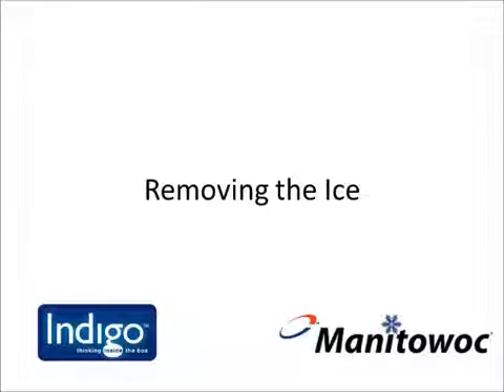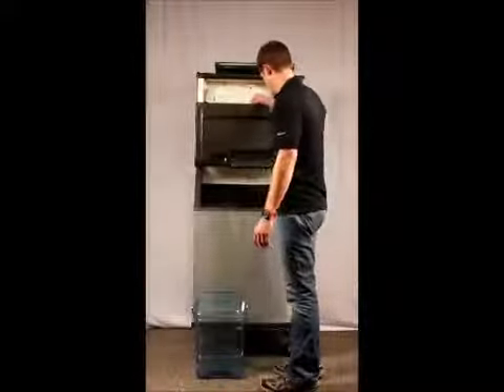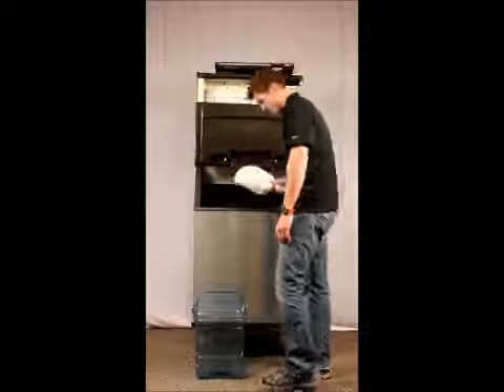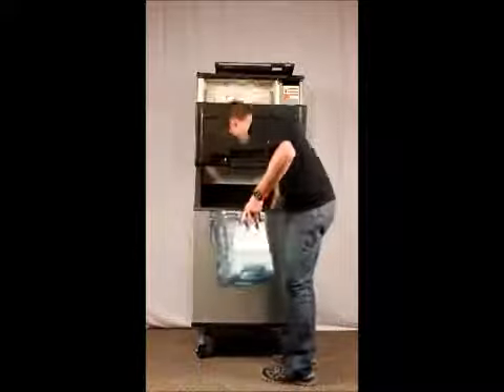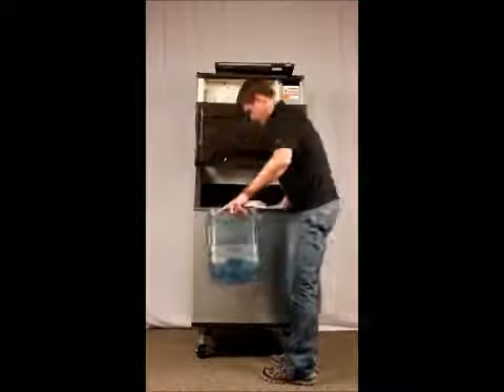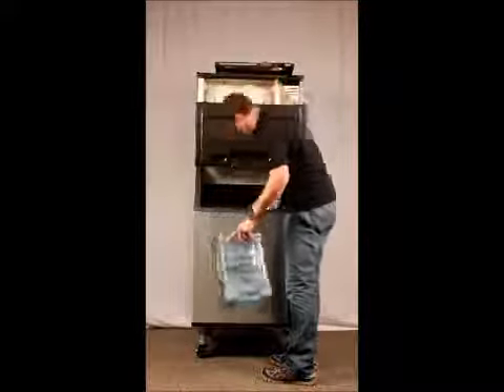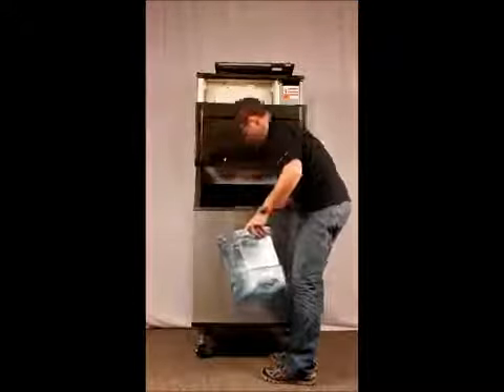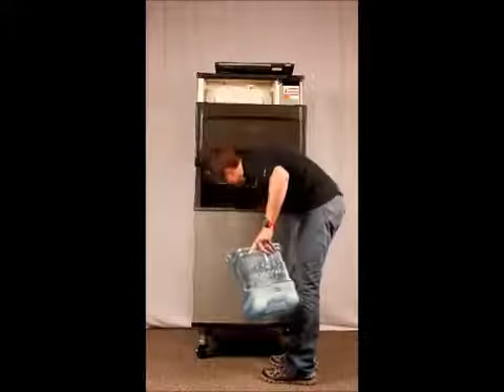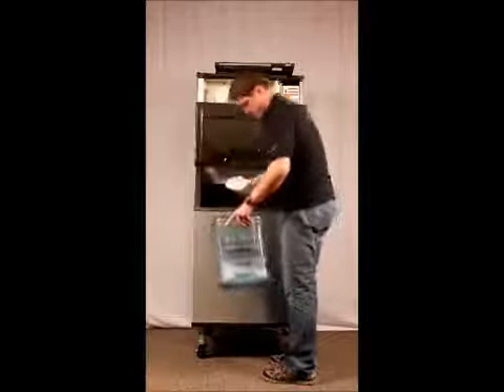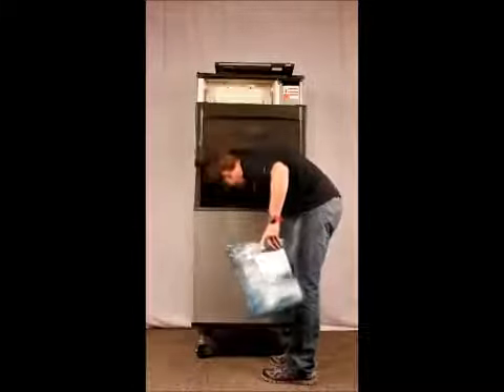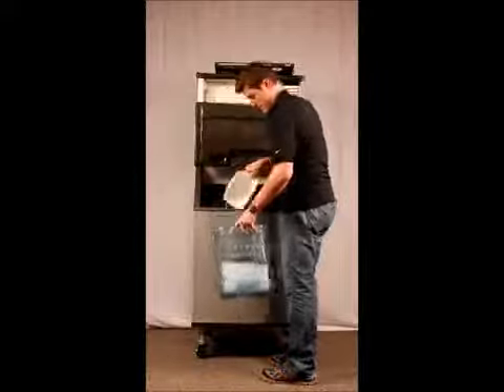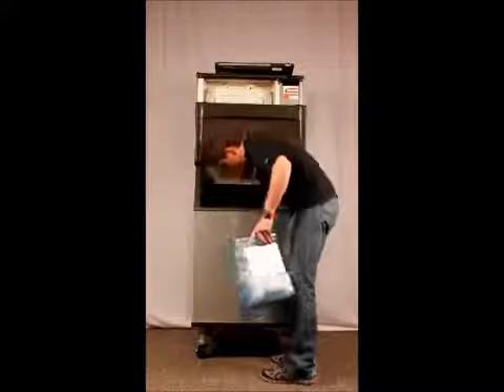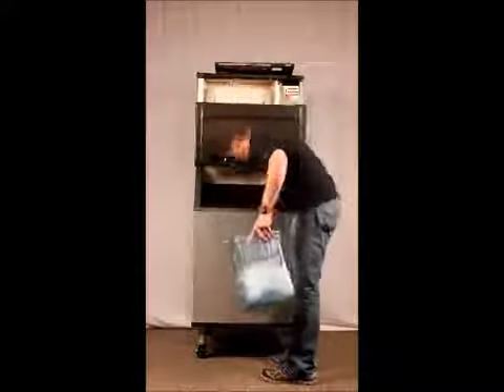Depending on the type of cleaning that is being performed, the ice may not have to be removed from the bin or dispenser. If the intent is only to clean the ice machine's water system and not do a more thorough cleaning that would require wiping down the sidewalls and removing parts from the food zone, then the ice can stay in the bin as long as Manitowoc Ice Food Safe Cleaner is being used. This product is citrus-based, so if a little bit of cleaner spills out onto the ice, it is not harmful if ingested.